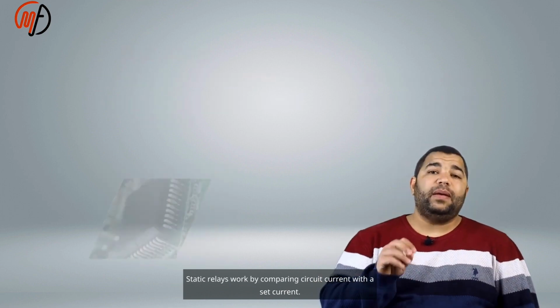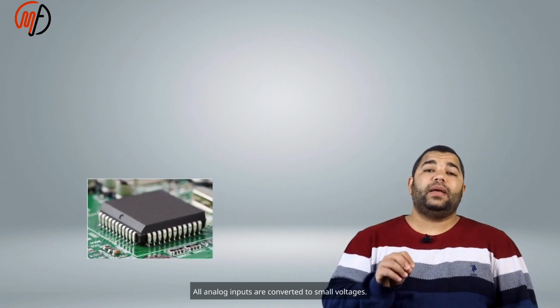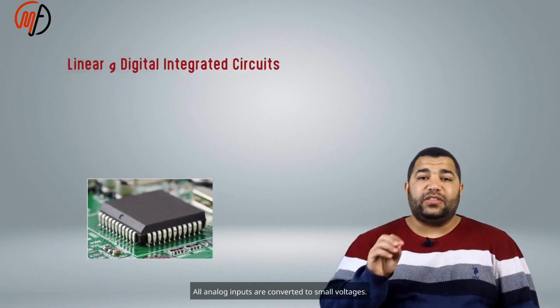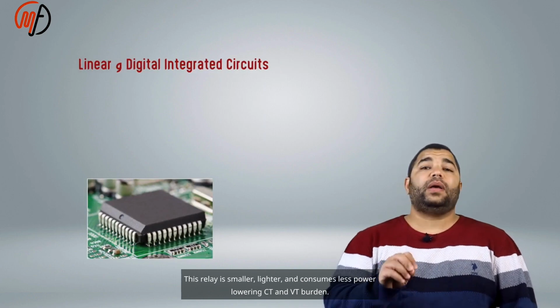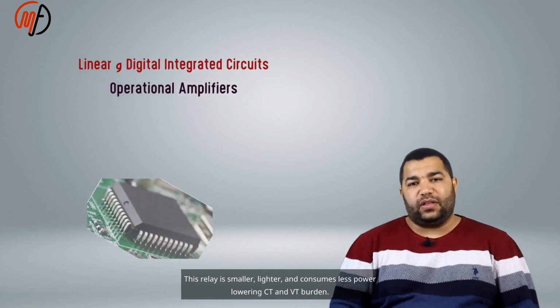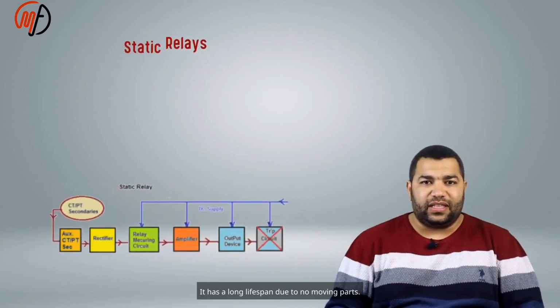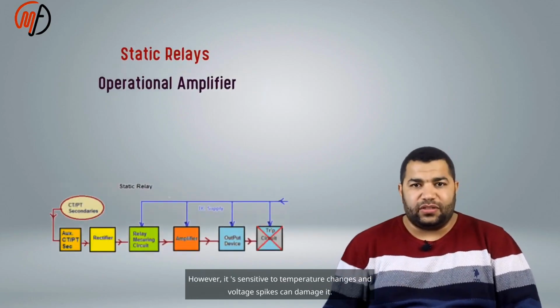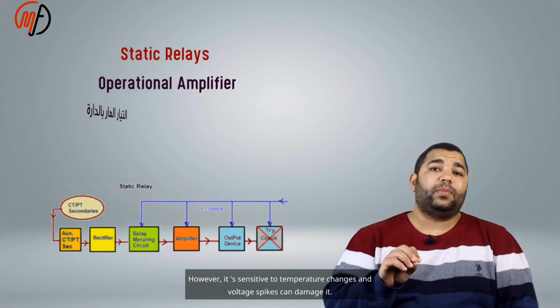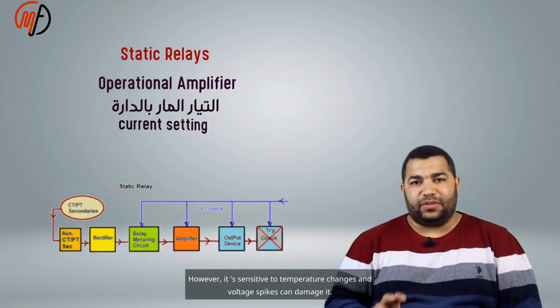Static relays work by comparing circuit current with a set current. All analog inputs are converted to small voltages. This relay is smaller, lighter, and consumes less power, lowering CT and VT burden. It has a long lifespan due to no moving parts. However, it's sensitive to temperature changes and voltage spikes can damage it.